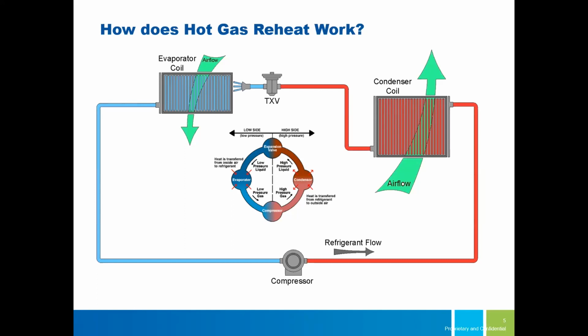What you see happening in a traditional refrigeration cycle is you've got low pressure liquid, and low pressure gas as you go through your evaporator. It becomes a high pressure gas after it's compressed. Then when the condensing process happens, that transforms into a liquid. Heat transfer is happening during these processes at the evaporator and the condenser. Then you've got an expansion valve, which allows your high pressure liquid to turn into a low pressure liquid. So that's the basics of the refrigeration cycle.